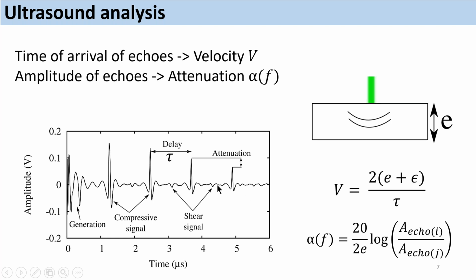Another parameter that can be interesting to evaluate is the attenuation. The attenuation corresponds to the decay between one echo and the subsequent echo. It can be evaluated in different manners, and often we look at this attenuation as alpha, which is a function of the frequency. So we know that this attenuation will be different at every frequency of these ultrasonic pulses. We divide by the propagation distance so as to have an attenuation per unit length, independent of the thickness of the sample.